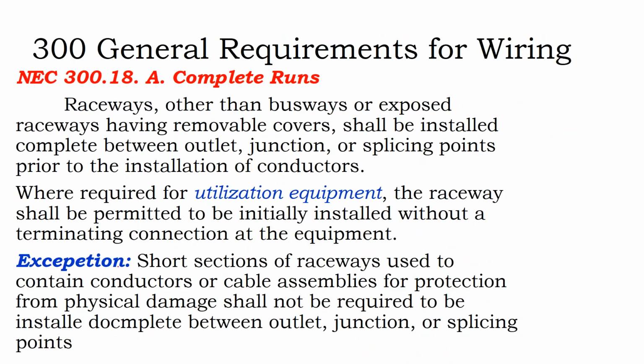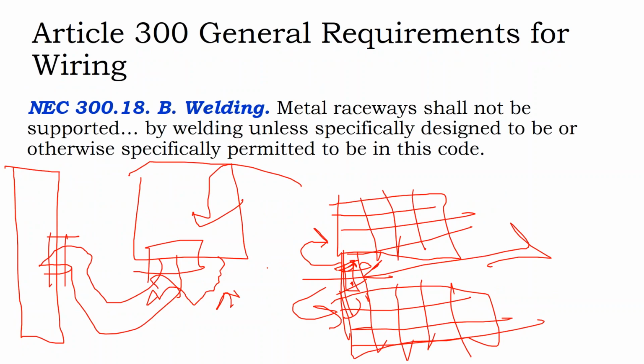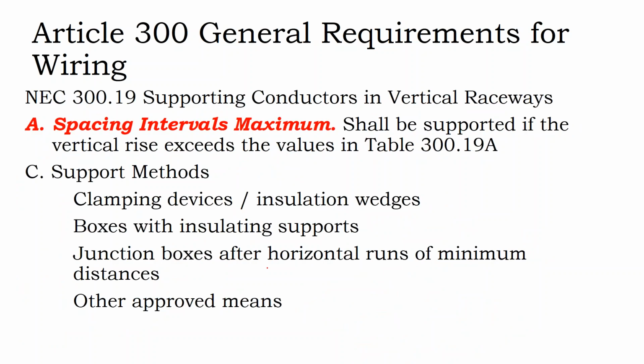So you're allowed short sections of raceways, really only used for protection from physical damage, and not used to connect multiple pieces of equipment together. Those short sections are not required to be installed in a complete manner. That still doesn't mean it's not a good idea to put smooth-edged bushings at the edge of those, or to even consider spacing the conduits out to better promote heat dissipation.